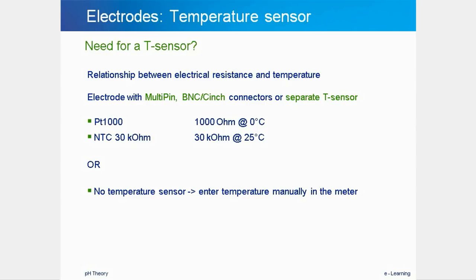When the sample is not at room temperature or is at varying temperatures, a temperature sensor is very useful to perform automatic temperature correction of measured pH values. The temperature can be measured with a separate temperature sensor connected to the pH meter, or with an integrated temperature sensor in the pH electrode itself. This can be done with multi-pin connection pH electrodes, which have connections via a BNC connector for the reference and pH electrodes and a Cinch connector for the temperature sensor. Built-in temperature sensors are available as PT-1000 or NTC.